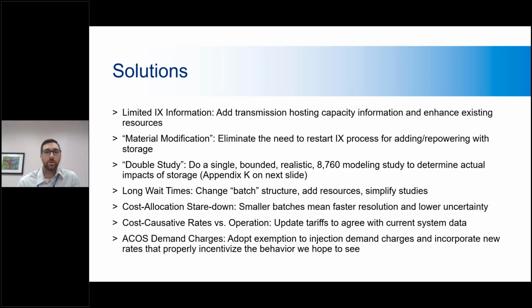In terms of the double study issue, where we're doing static single hour worst case scenarios for off peak and on peak, what we've really been pushing for is a more realistic, bounded 8760-style hourly modeling study to see what an actual storage project would actually do at these sites and how that impacts the system. Then build a flexible interconnection agreement around that study so you can really lower interconnection costs. You can charge people if they end up breaking this interconnection agreement, but your base level interconnection upgrades won't be based on this very unrealistic operational profile.